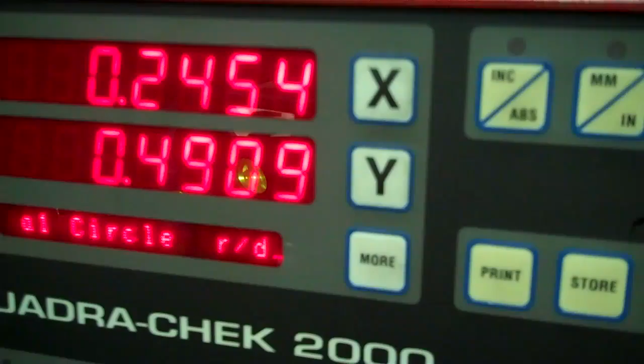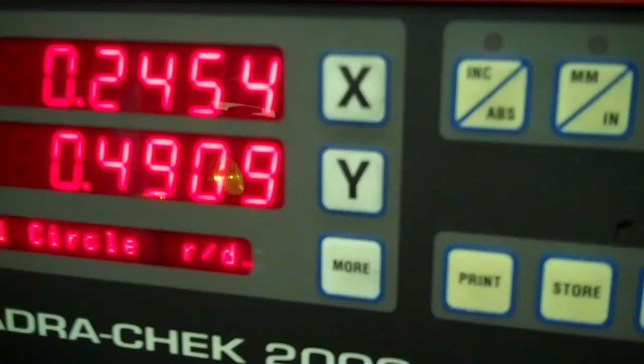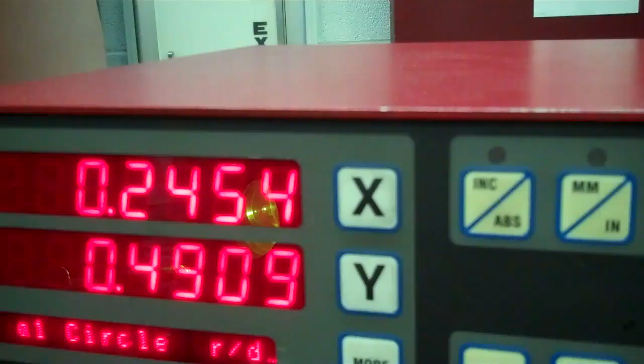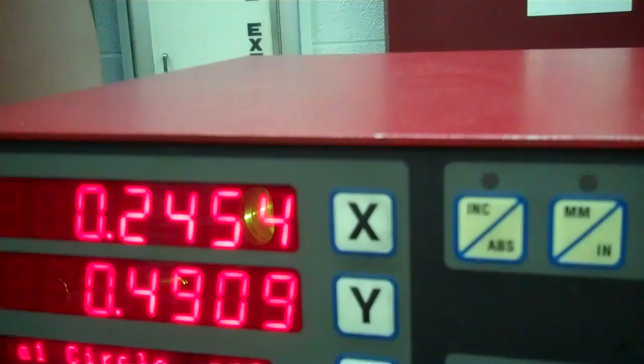Now whenever we look at these numbers, the top number would be the radius, 0.245, the bottom number would be the diameter, 0.490. Alright, if that is a 1/4 inch radius gauge, that's saying it's within 5/1000ths of being an actual 1/4 inch. Now it may have a little bit of wear on it, and if we want to double check it, we can probe it again. The more places you probe it, the more accurate it would be.